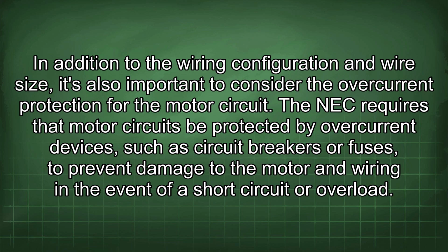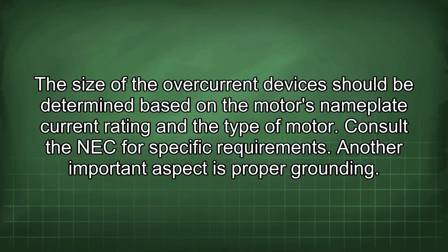In addition to the wiring configuration and wire size, it's also important to consider the overcurrent protection for the motor circuit. The NEC requires that motor circuits be protected by overcurrent devices such as circuit breakers or fuses to prevent damage to the motor and wiring in the event of a short circuit or overload. The size of the overcurrent devices should be determined based on the motor's nameplate current rating and the type of motor. Consult the NEC for specific requirements.